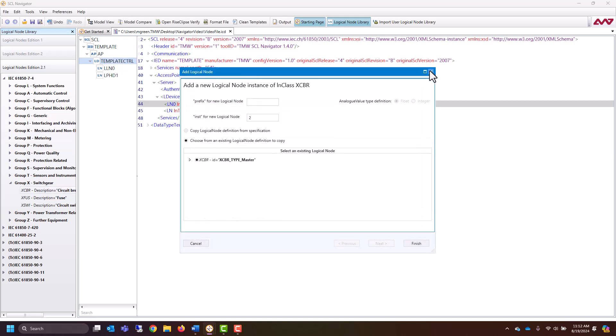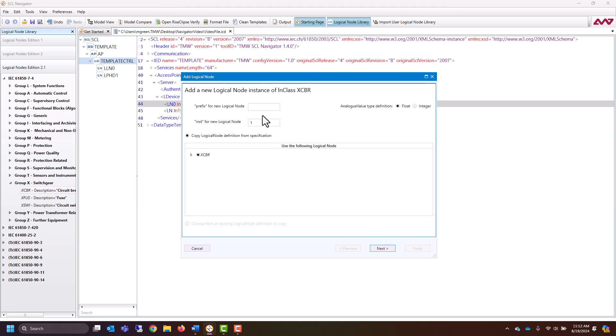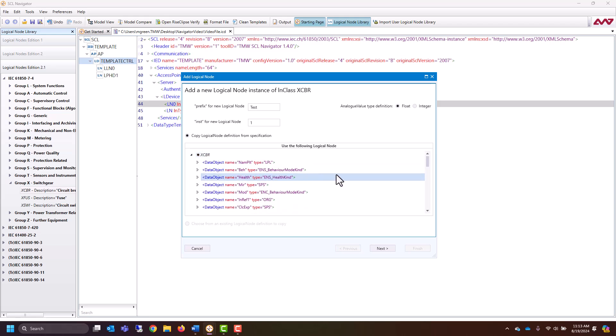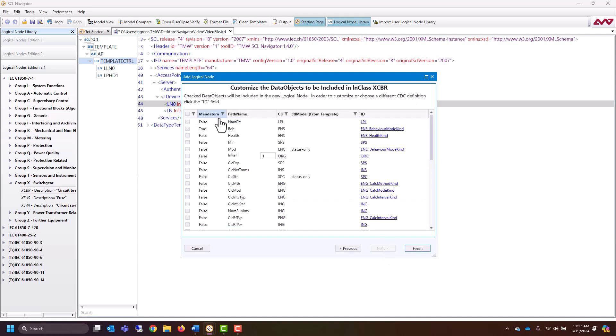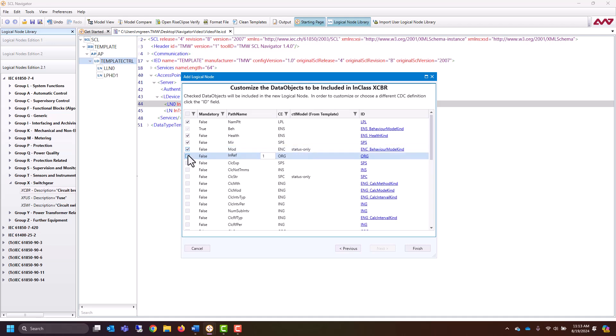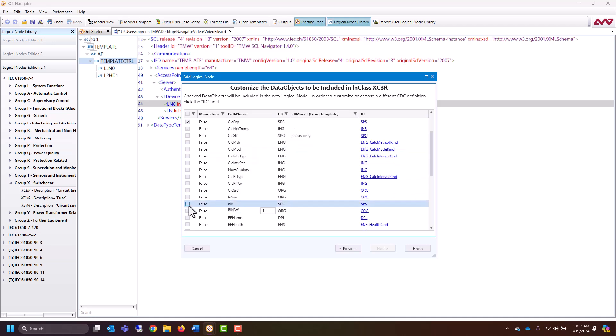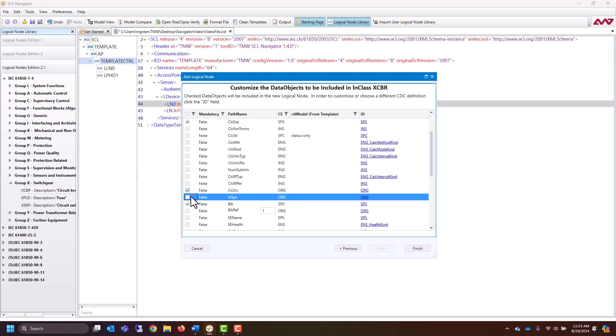This will bring up a context menu for the logical node that we dragged over. You can give it a prefix and an instance number. You can see all the different data objects that can be inside. Then if you hit Next, it'll bring up all of the fields that are either mandatory or optional. You can go in and select which parts of this logical node you would like to bring in, and then click Finish.